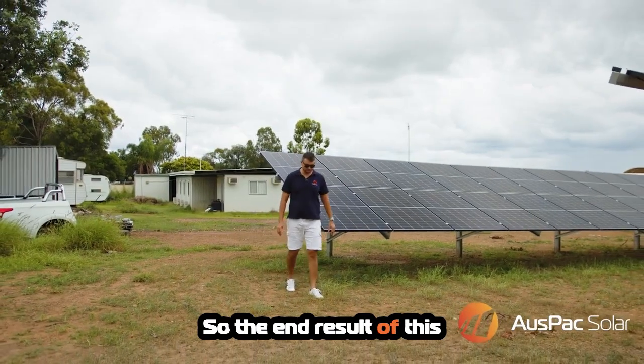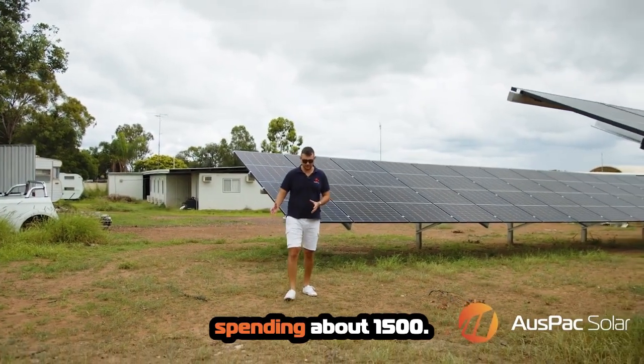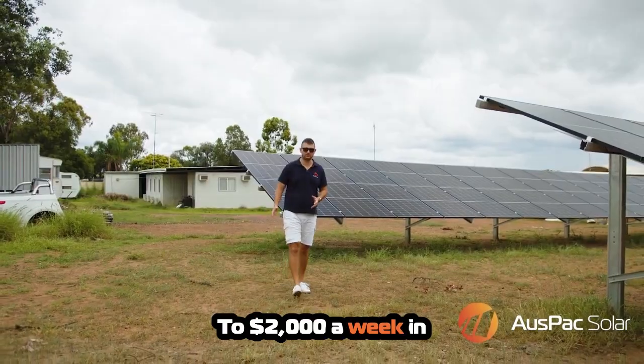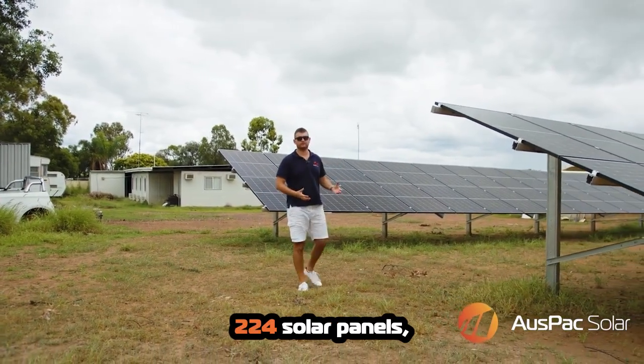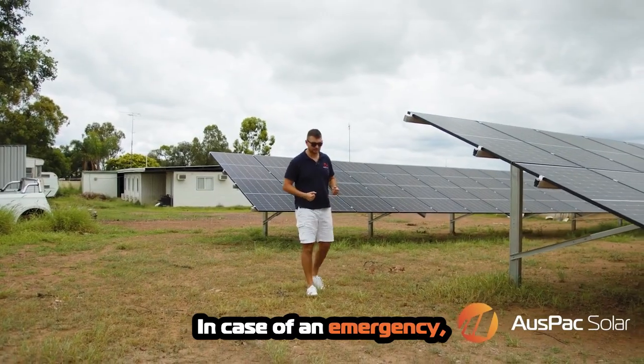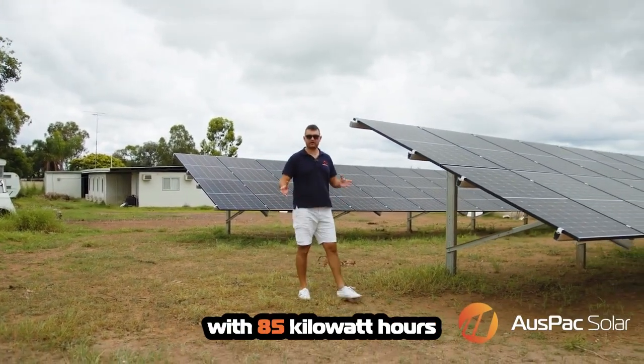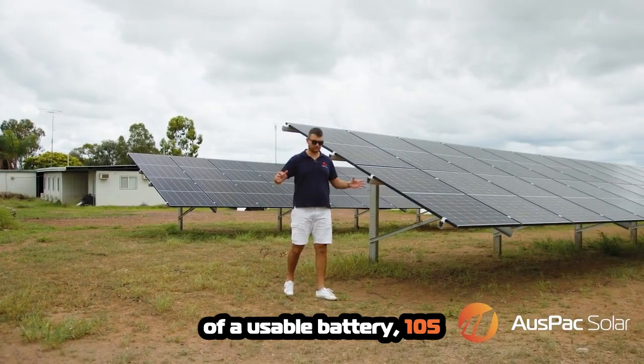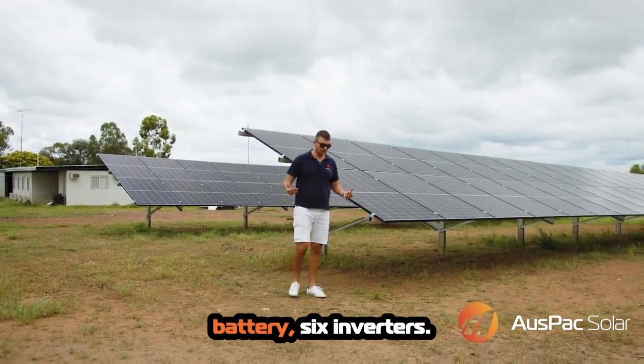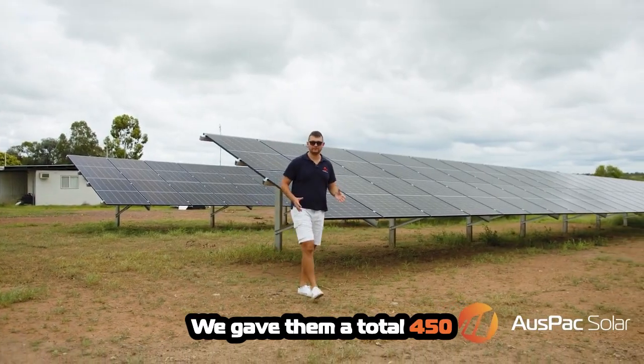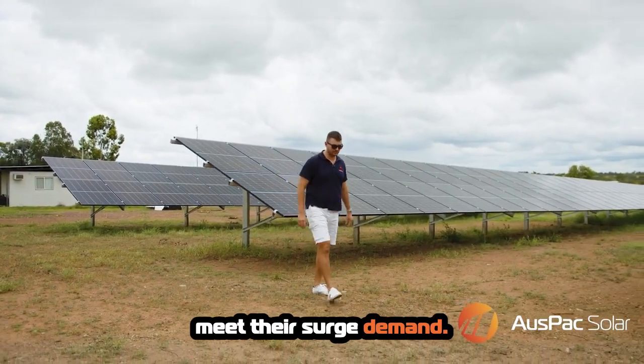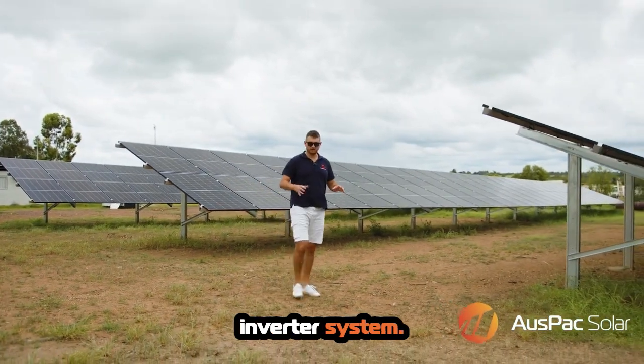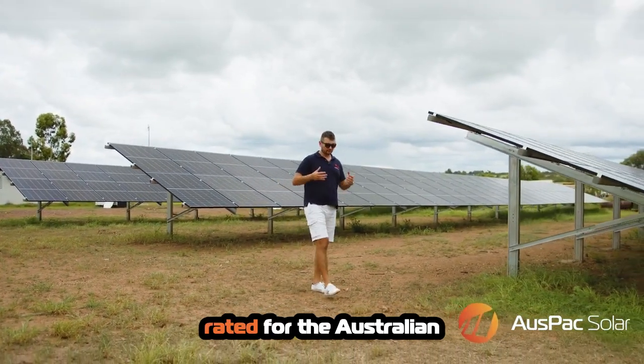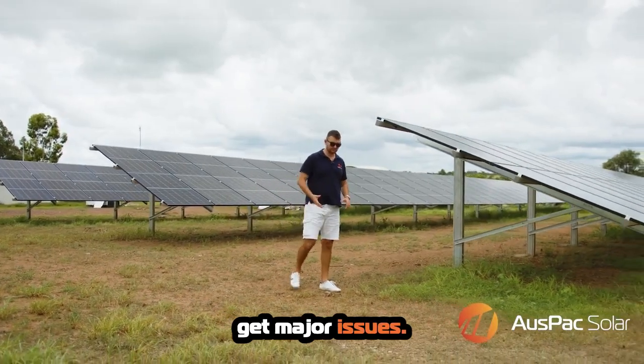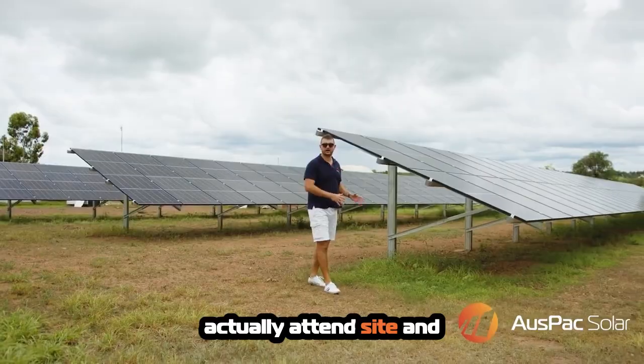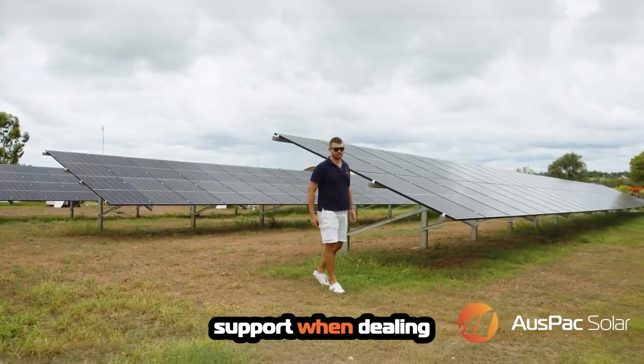So the end result of this system for the customer, originally they were spending about $1,500 to $2,000 a week in diesel. We've installed 224 solar panels, gave them spares in case of an emergency. We installed 18 batteries with 85 kilowatt hours of usable battery, 105 kilowatt hours of actual battery, 6 inverters. We gave them a total of 450 amps output so we could meet their surge demand. We also used an inverter system that was IP55 and 65 rated for the Australian heat, so that we don't get major issues. We had Solax engineers actually attend site and commission the site, so they give us on-site support when dealing with AusPac Solar.